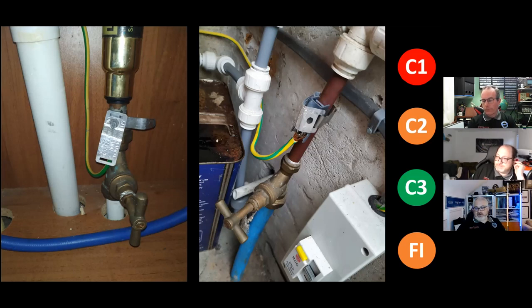But I do think in the near future we'll do a separate webinar on this, because we're looking at diverted neutral current phenomena. We're looking at a number of issues with network stability and network configuration. And I think it's fairly evident to say, based on the research that we have been doing, the networks are a bit of a mess. We need to untangle this web so that we can present it to you guys. But I've always believed that bonding, regardless whether you have an insulated insert, I would just do it. Although whoever put that cable on the right-hand side one needs to use a crimp lug, because I hate seeing that, because any unskilled person can just pull that out.